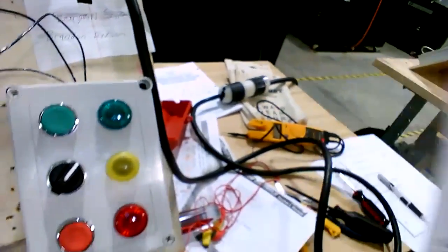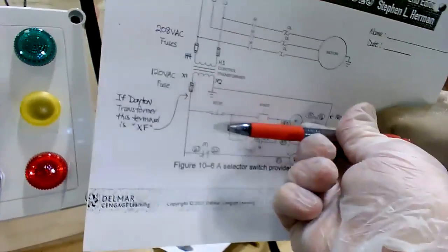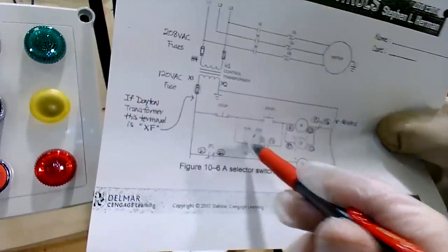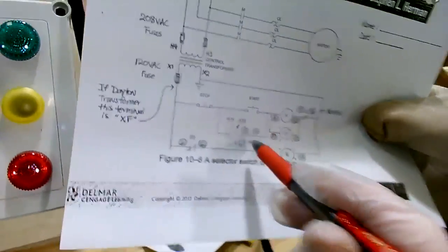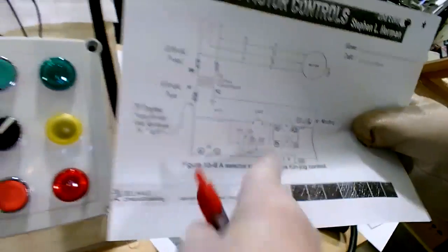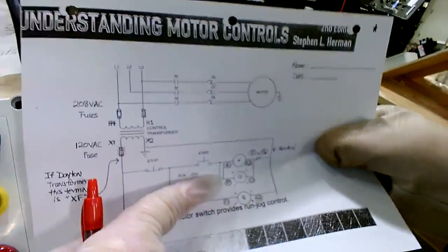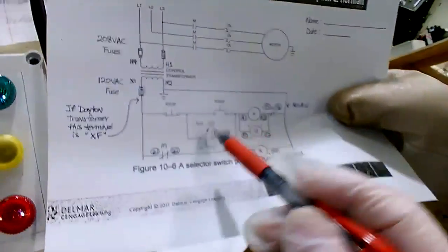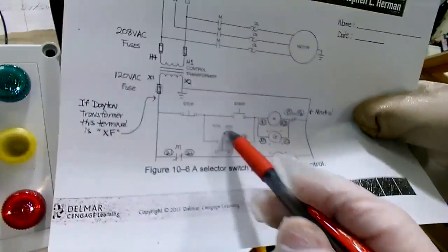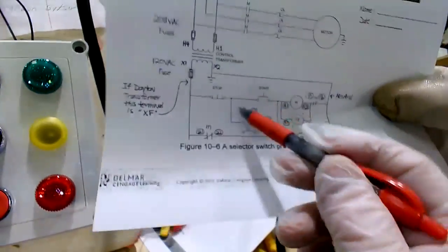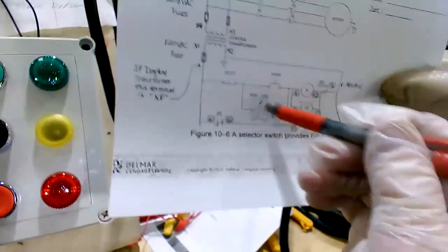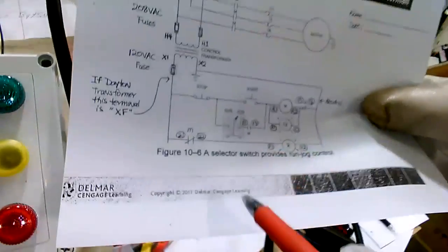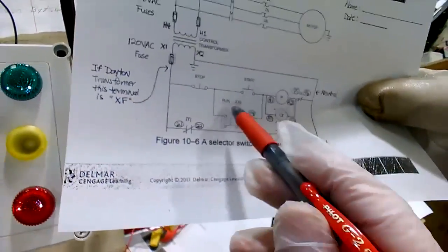So the way you create a jog situation is you interrupt it like we did right here. This switch, when it goes in jog, the contact goes down. It disconnects 13 so that this can't hold. So it basically takes power off of 13 so that you're stuck with a series circuit that's just a push button with no holding contact. It takes power away from the holding contact and you put your switch up like this. If you go to run, that contact goes up, it restores contact there like normal.